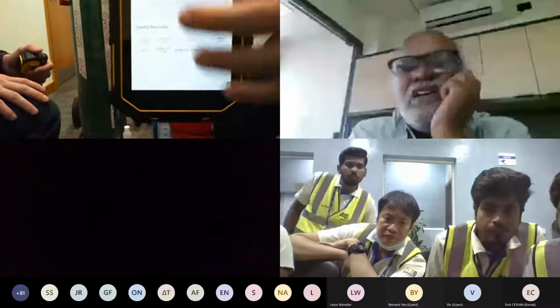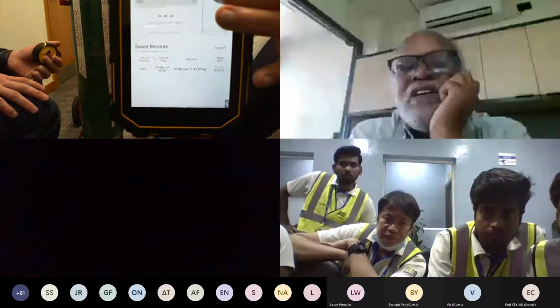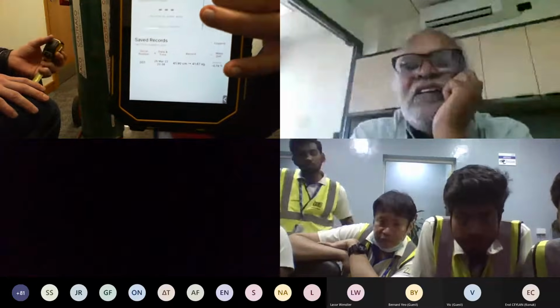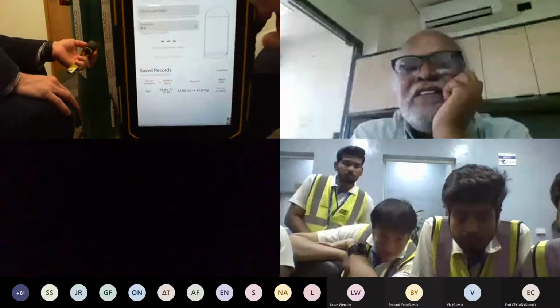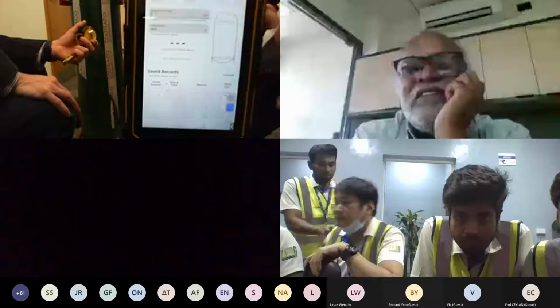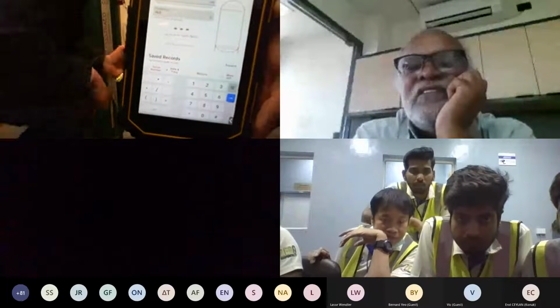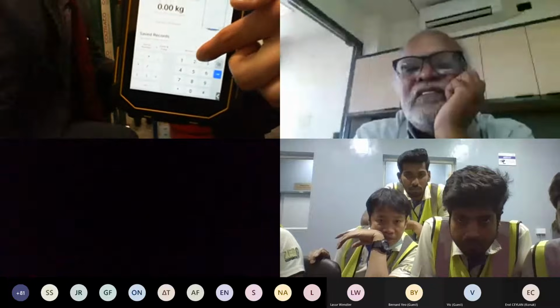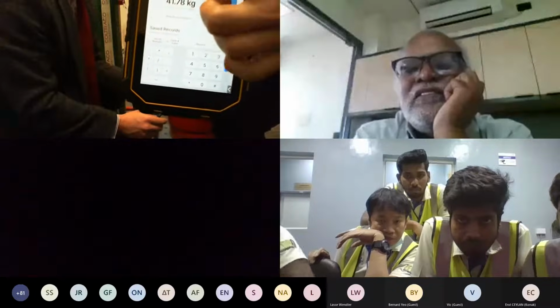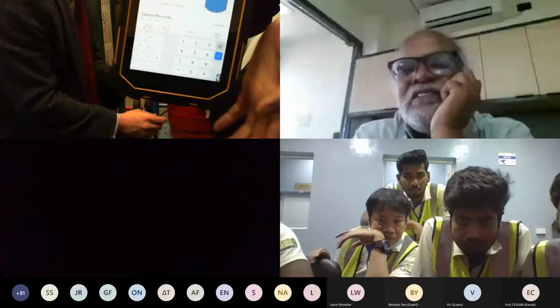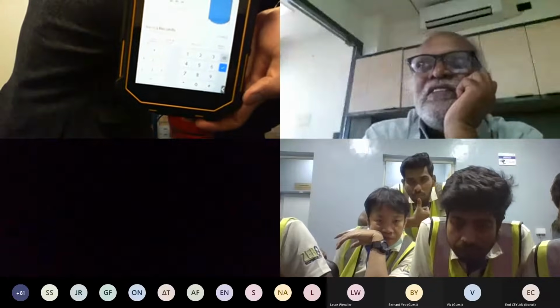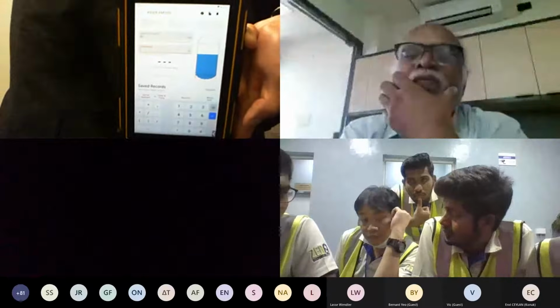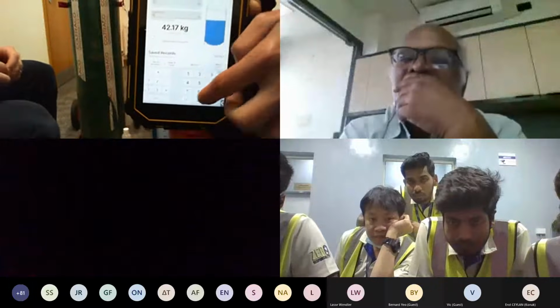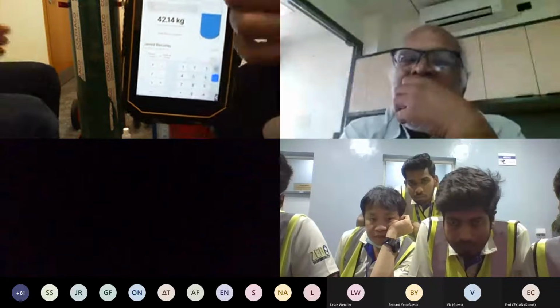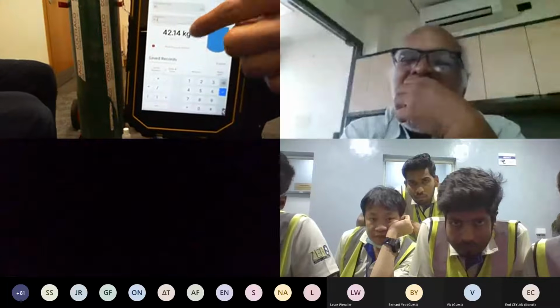Just click done. And similar to the CO2 cylinder, all you have to do is input the liquid level height and the temperature, and it will calculate the corresponding agent weight for you. Okay, Benjamin, what is the liquid level height? It's 42 centimeters. So the liquid level height measured is 42 centimeters. Okay, and can you measure the temperature, please? Yes, it's sitting around 11.2. So the cylinder, this is a 42 kg FM200 cylinder.